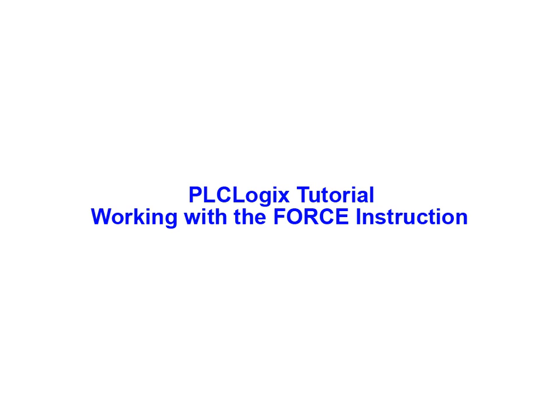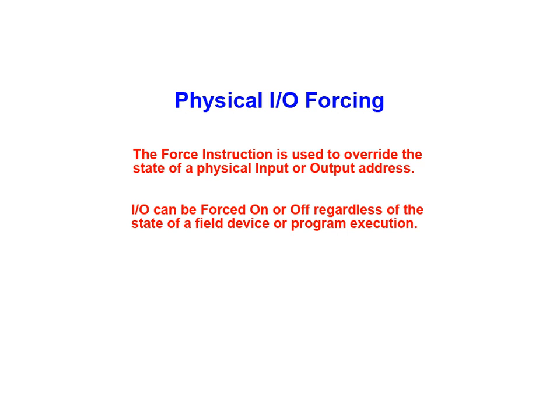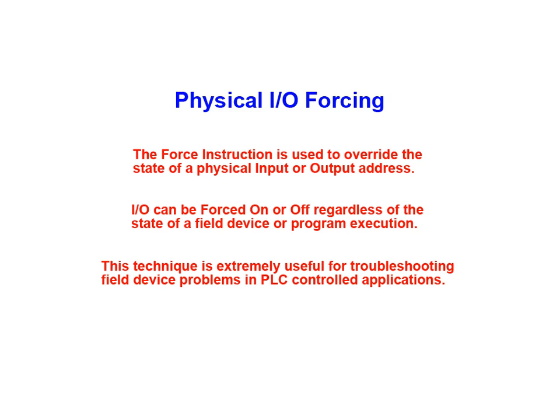In this animation, we'll be examining how I/O forces are accomplished using the PLCLogix simulation software package. The force instruction is used to override the state of a physical input or output address. I/O can be forced on or off regardless of the state of the field device or program execution. This technique is extremely useful for troubleshooting field device problems in PLC-controlled applications.